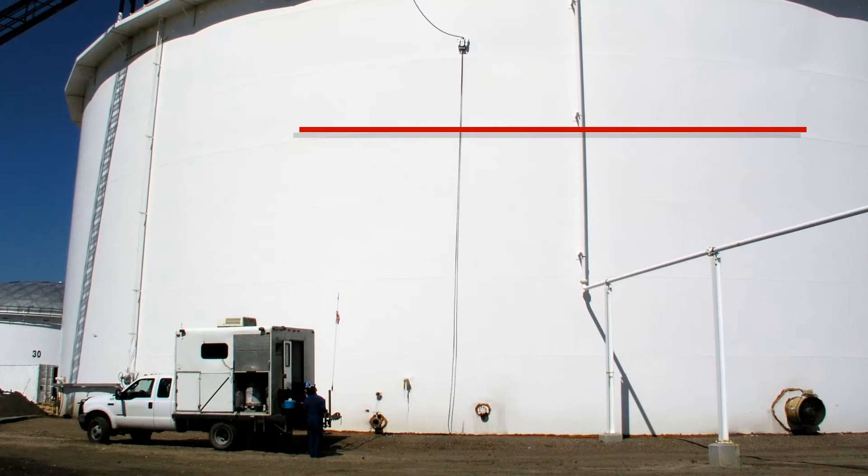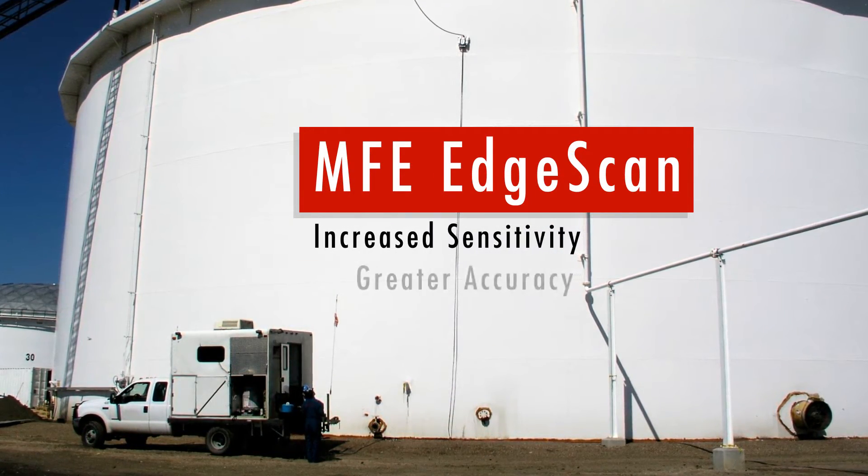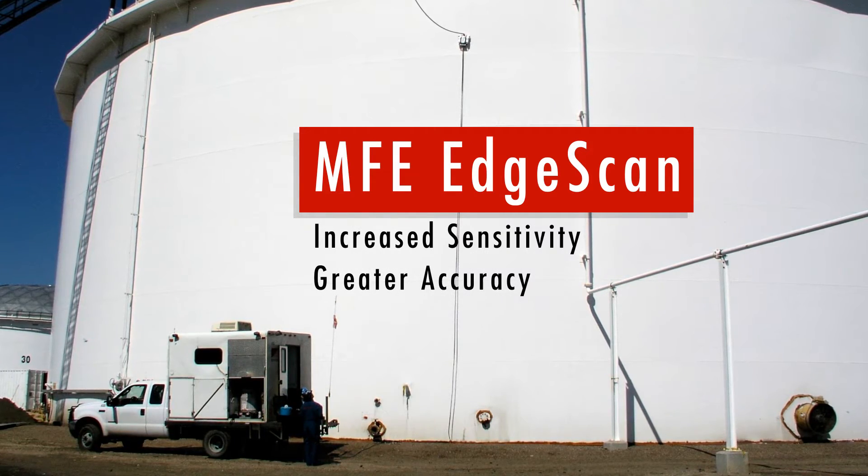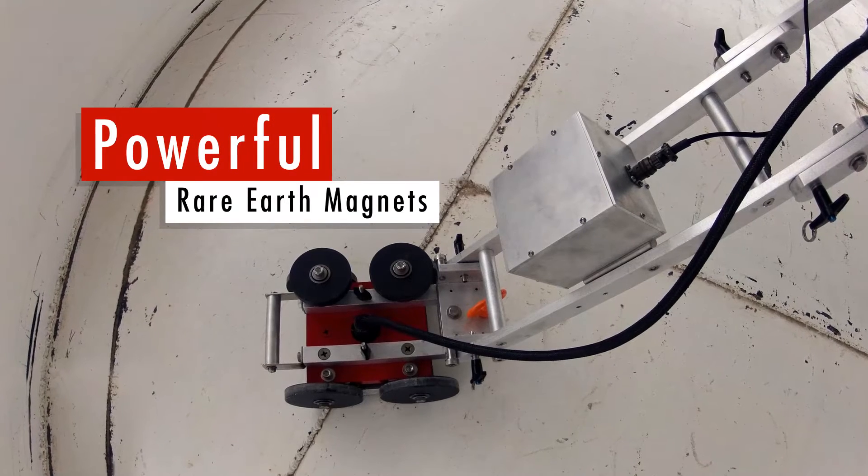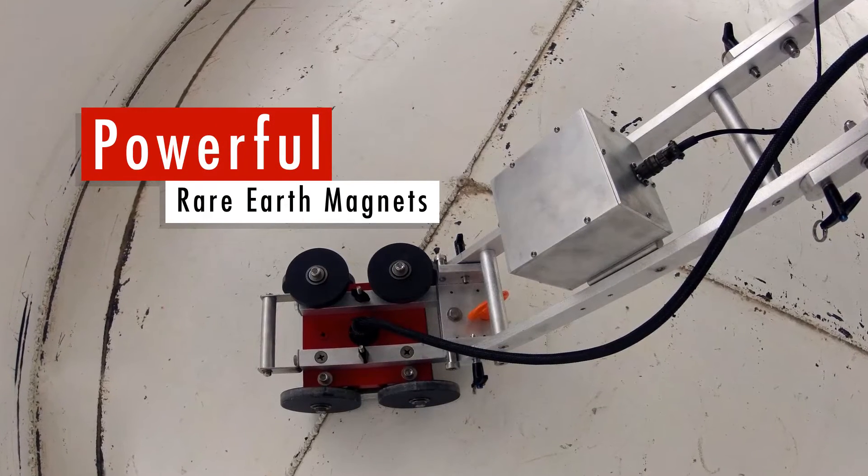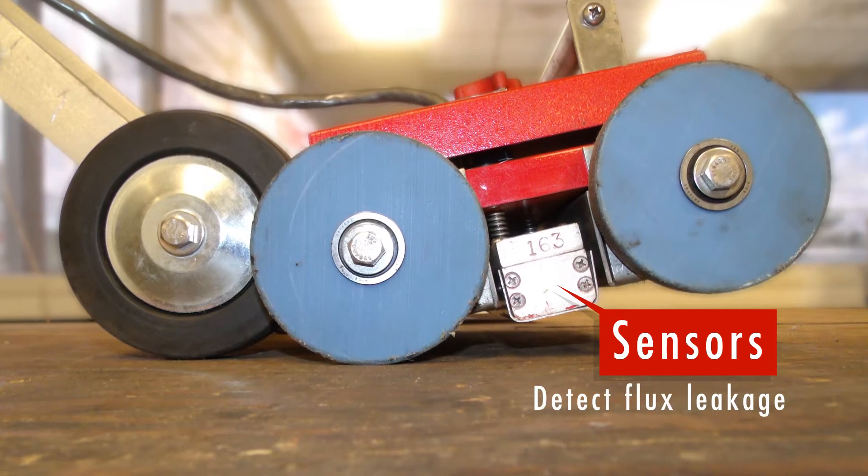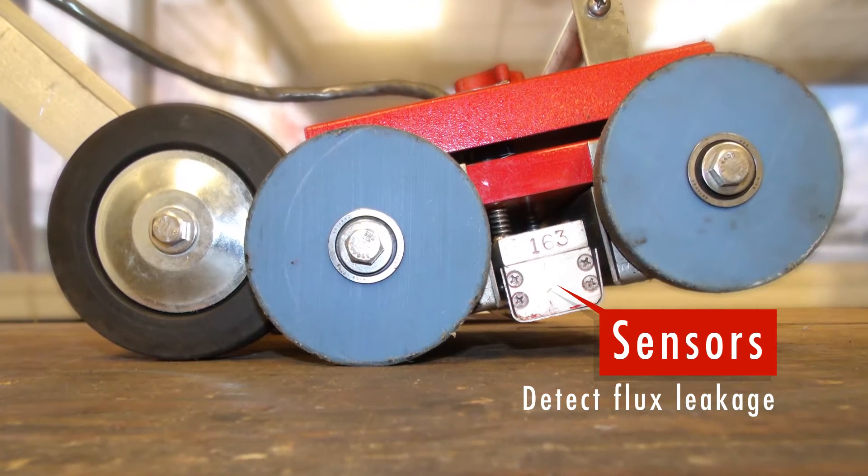Improving over previous models, the edge scan offers increased sensitivity and greater accuracy than any other MFL scanner before it. The magnetic bridge contains powerful rare-earth magnets to magnetize and saturate the tank floor plates, while sensors attached to the unit detect flux leakage caused by volume loss.